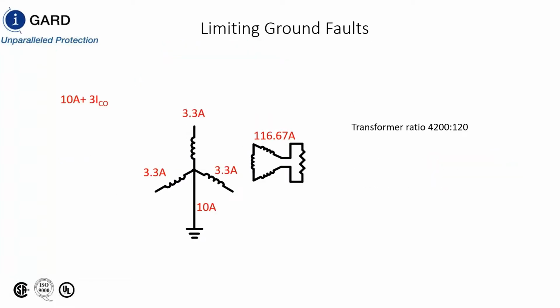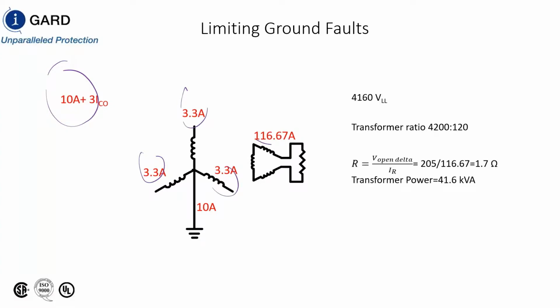So typically this example is used for a high resistance grounded system, because if you limit the fault current to 10 amps, now there's 3 1/3 amps flowing through each phase, 116 amps flowing there, and you just put a 1.7 ohm resistor. So we've used this system for high resistance.